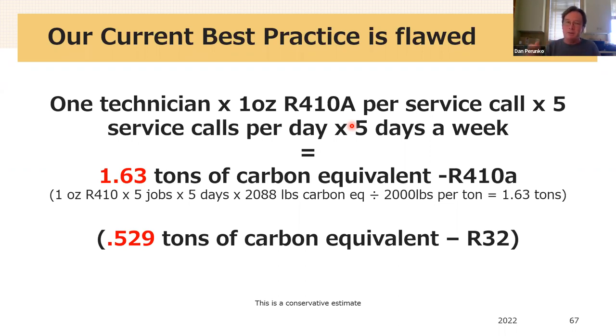So you have a person, and they go out and they connect to the system, they do their adjustments, they disconnect, they release the refrigerant in their tool, and they've released 1 ounce of refrigerant. And that person goes to 5 places every day, and they work 5 days a week. So they're releasing 25 ounces of refrigerant per week, which is equivalent to 1.63 tons of carbon. It's a huge amount of carbon being released by servicing air conditioners and heat pumps, right? We're over 1.5 tons just by service.